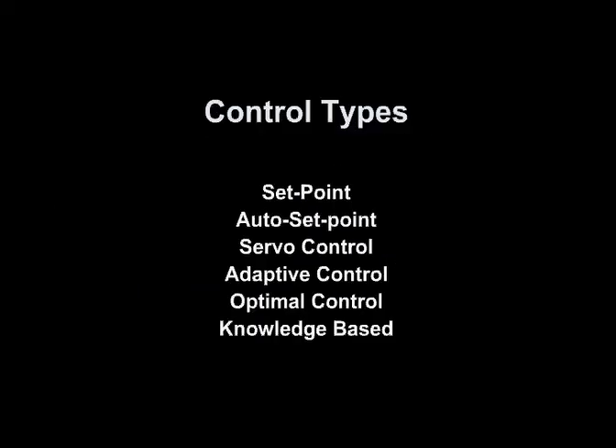Now, Control Types. The Control Type is a categorization of the feedback control function that the ventilator uses. We're going to start from the most basic, which is set point control, to the most advanced. There's a hierarchy of the evolution of ventilator modes. Currently in the United States there are six control types on mechanical ventilators in operation.